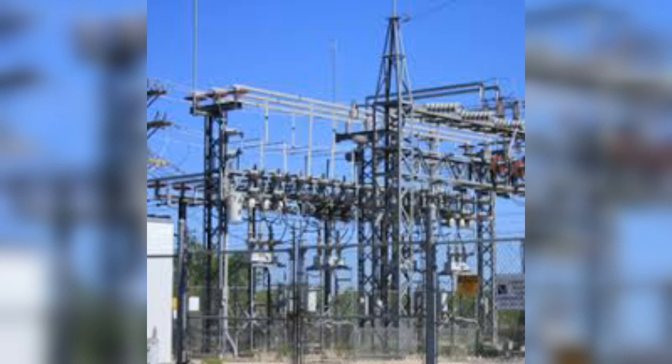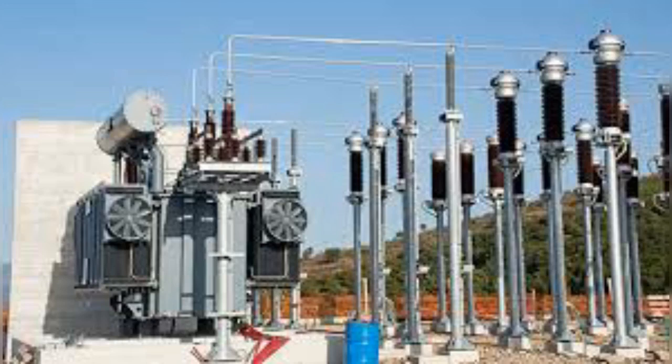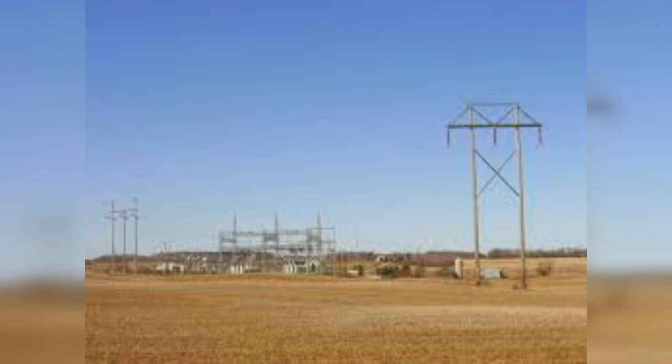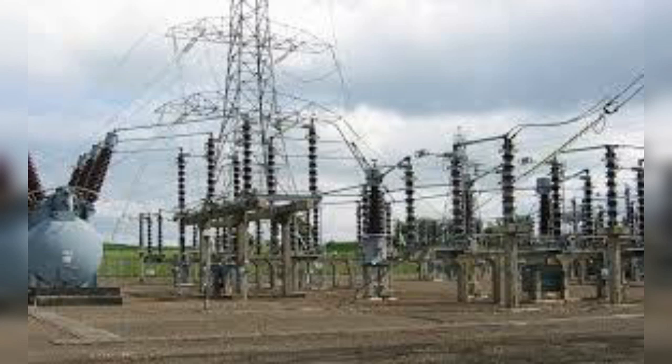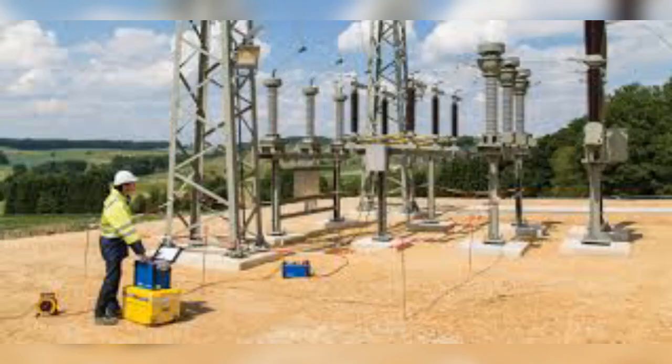The paper addresses the recommendations for testing BCTs safely and accurately in EHV stations, and discusses the different sources of undesirable electrical signals that can be induced in a measurement circuit, and techniques such as smart grounding principles. Smart grounding principles are shown to improve electrostatic performance and make the test setup immune to external factors.